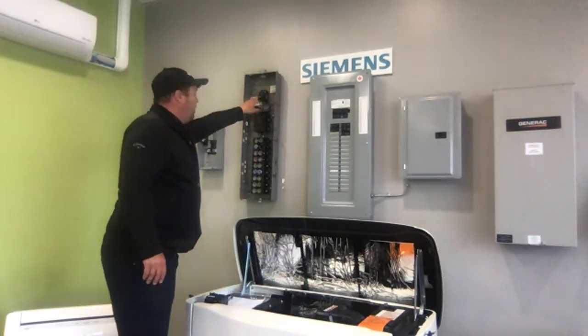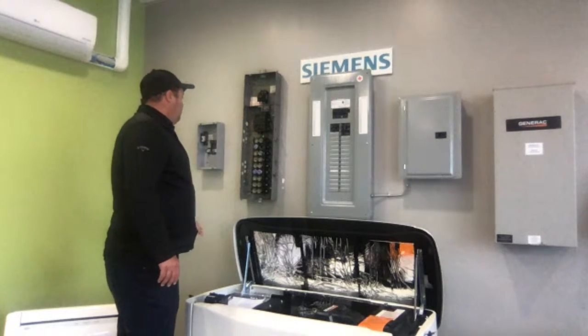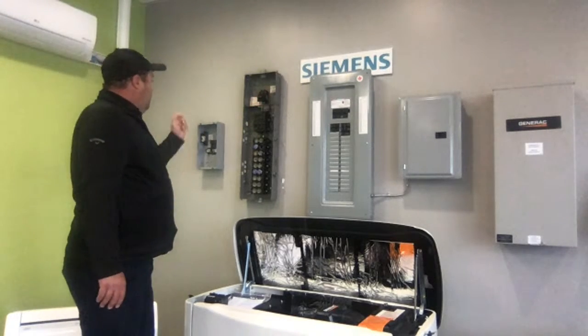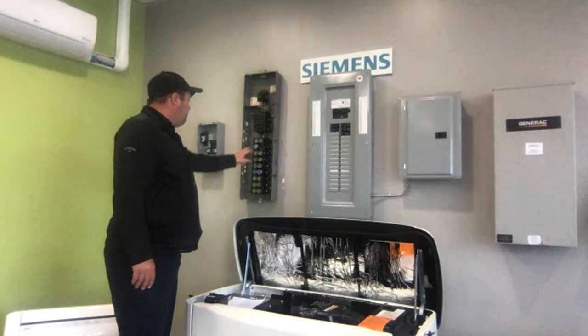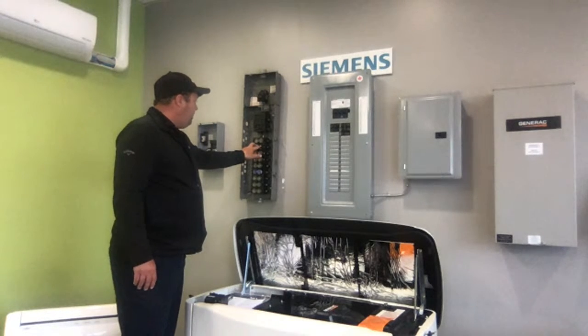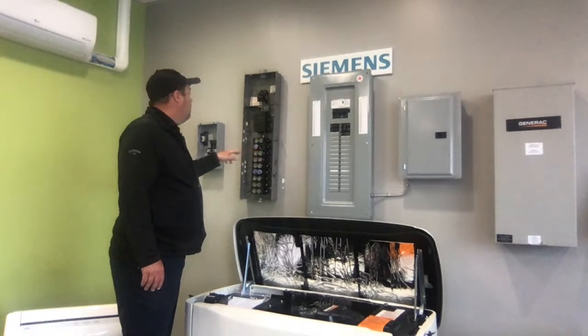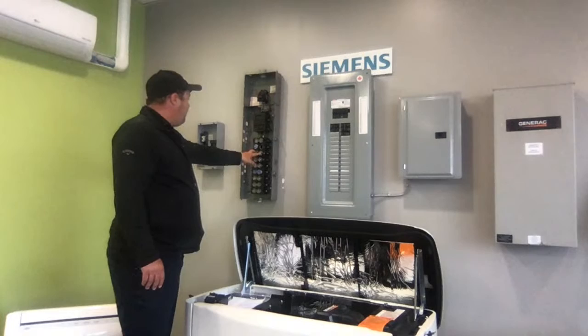And then we have kind of our old glass fuse panel, right? These are horrible panels, but they still work. So if you have 2 spaces, I need 2 spaces for every heat pump I put in. So if you're putting in 2 heat pumps, I need 4 spaces. If you're putting in 3 heat pumps, I need 6.